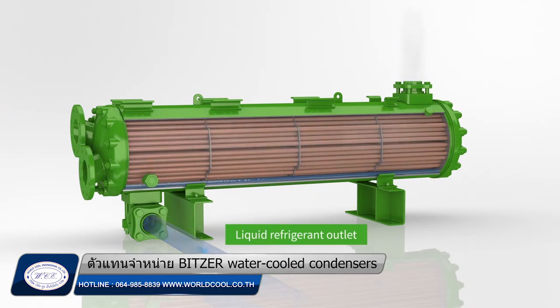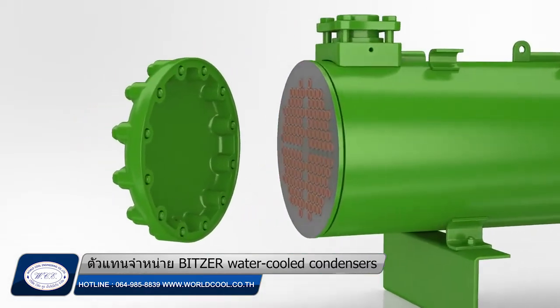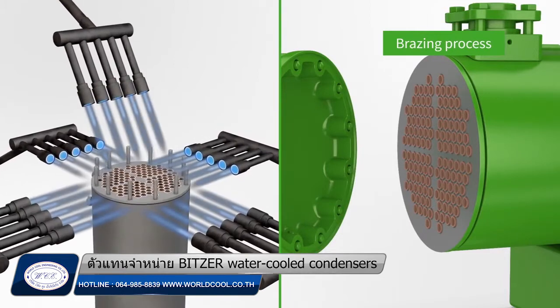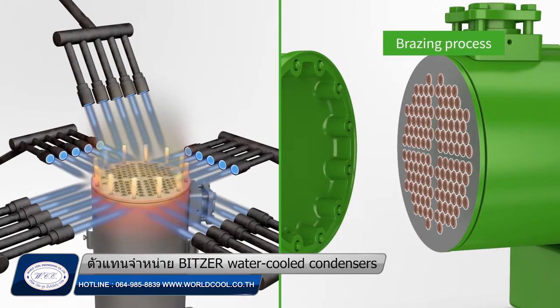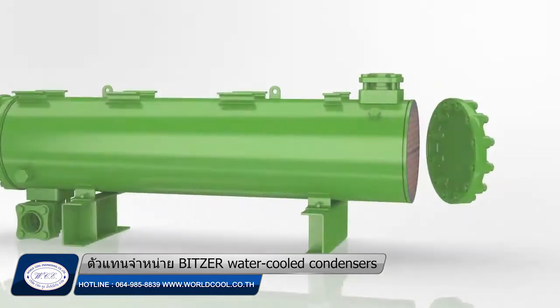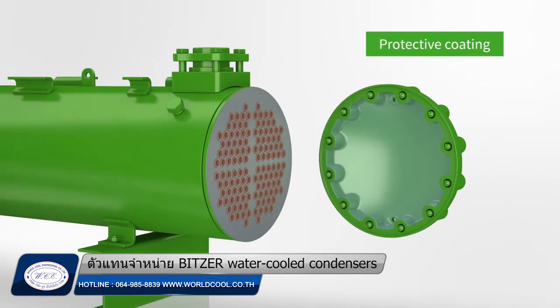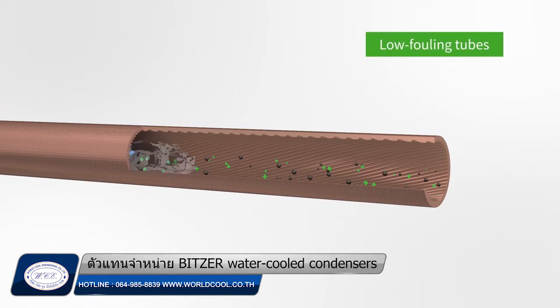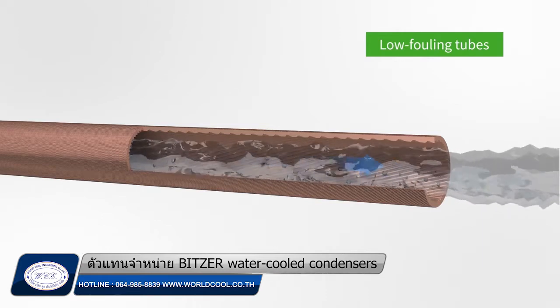The unique construction features of BITZER condensers ensure superior reliability in stationary, marine, and offshore applications. Tubes are jointed to the tube sheets with a unique homogeneous brazing process, ensuring superior resistance to thermal and mechanical fatigue — a key factor for the longevity of BITZER condensers. A coating is applied to protect tube sheets against corrosion and erosion risks. The special low-fouling inner design of the tubes helps the water to self-clean any deposit, allowing consistent performance during the entire life of the condenser.